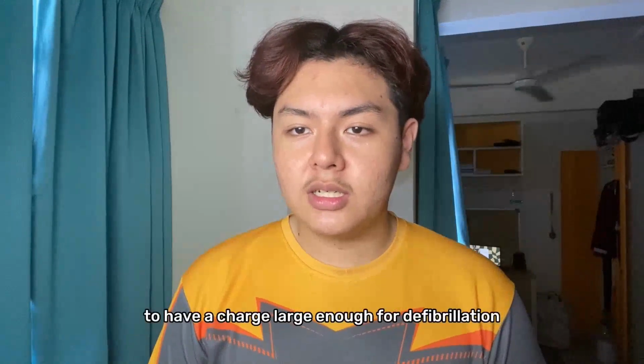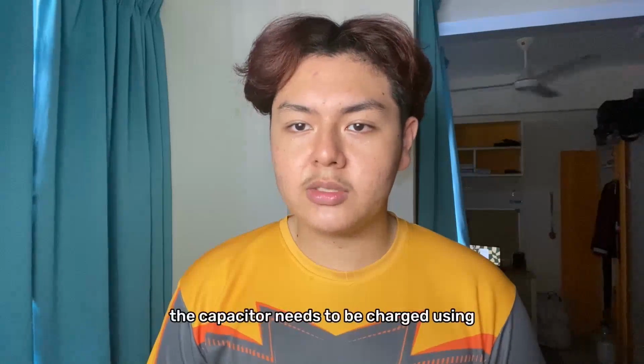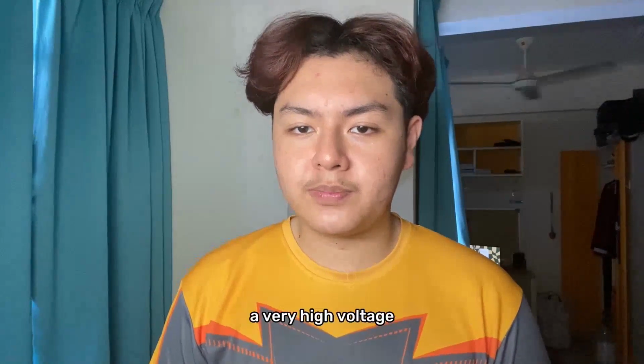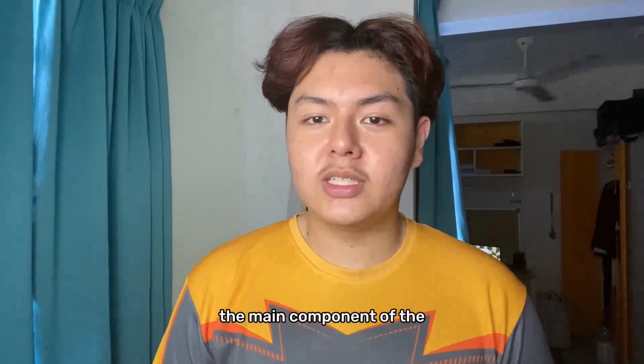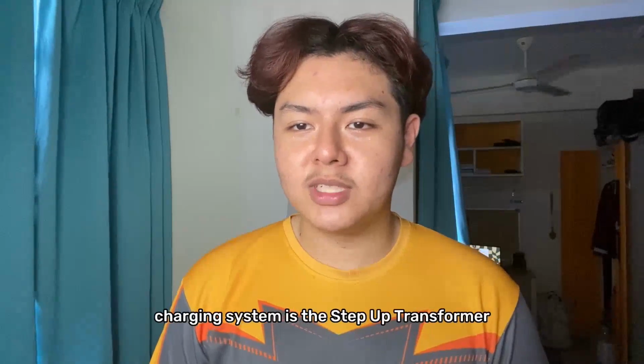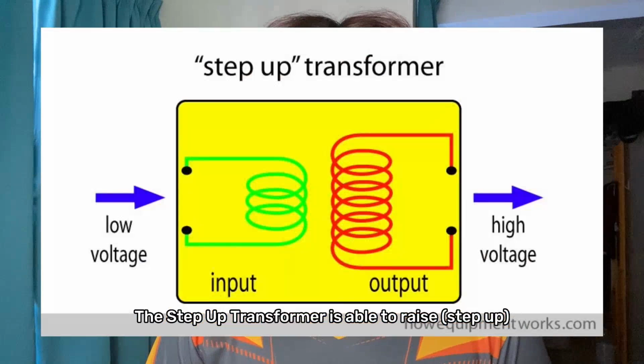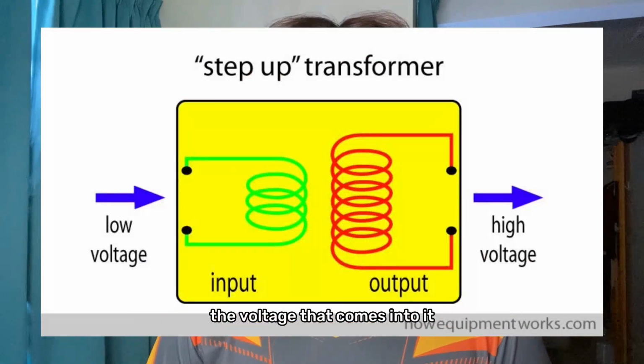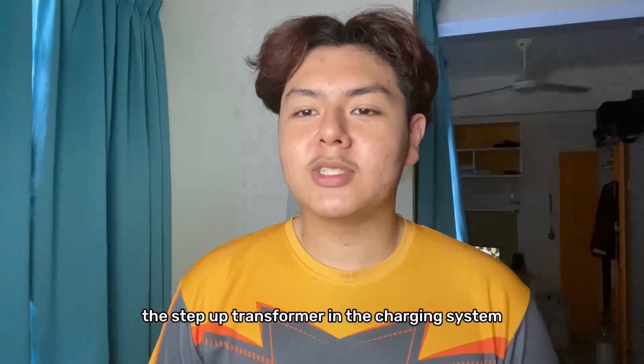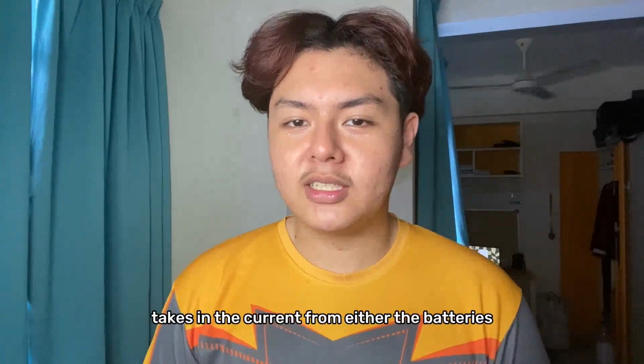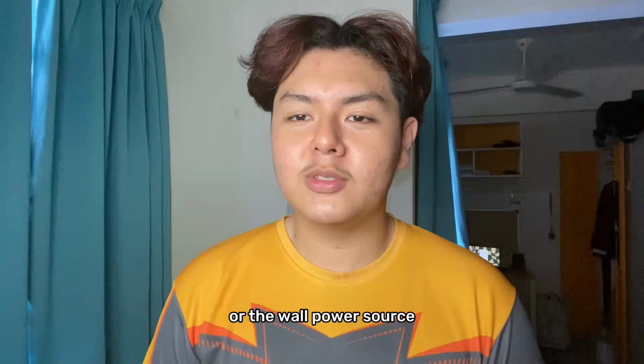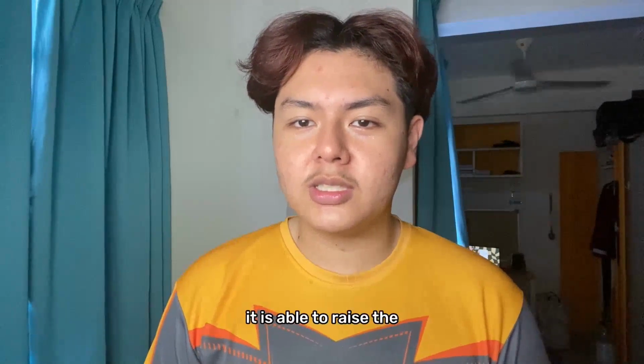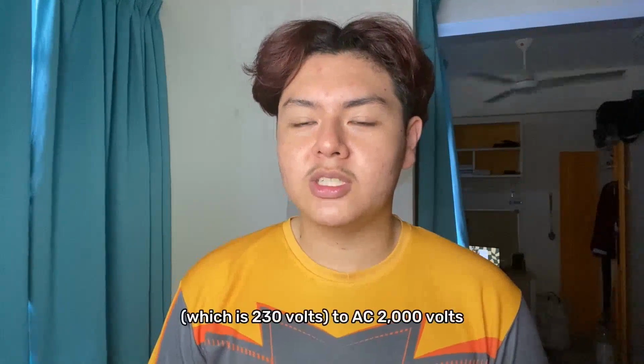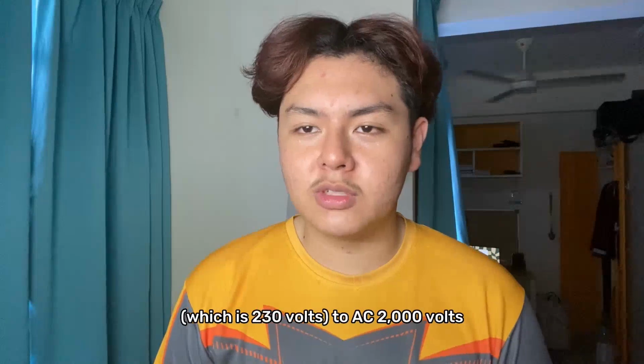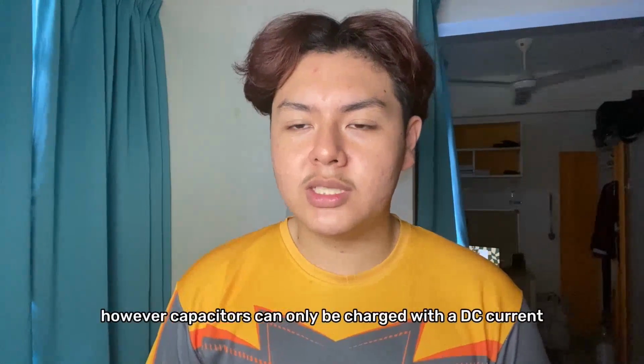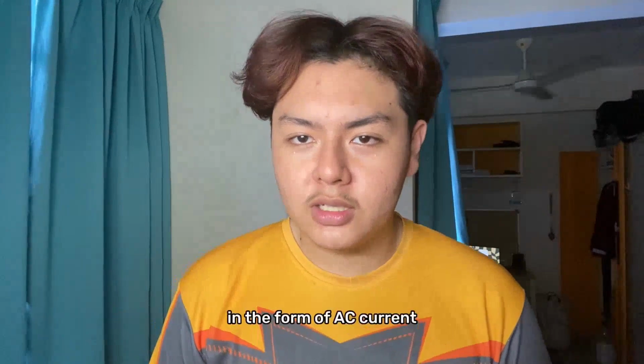To have a charge large enough for defibrillation, the capacitor needs to be charged using a very high voltage. The main component of the charging system is the step-up transformer. The step-up transformer is able to step up the voltage that comes into it. The step-up transformer in the charging system takes in the current from either the batteries or the wall power source. For example, it is able to raise the supply voltage from the wall power source, which is 230 volts, to 2000 volts. However, capacitors can only be charged with a DC current, whereas the step-up transformer puts out AC current.